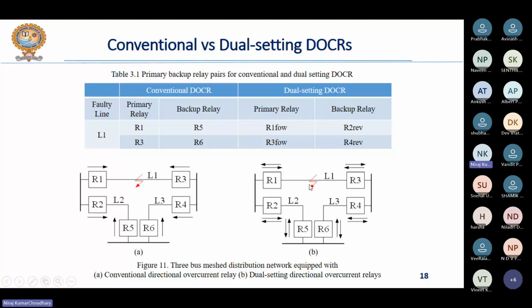if a fault occurs at R1, L1 on this line, the same fault location, and you have considered R1 as the primary relay, then R2 will be the backup relay. And if R3 is considered as the primary relay for the same fault location, then R4 will be the backup relay, right? So this is one of the changes due to which the overall time of operation of the relay after the occurrence of the fault reduces in case of dual setting directional overcurrent relay. That you can observe, meaning later on you will see in the result section the comparison between the time of operation of the dual setting DOCRs and the conventional DOCRs.